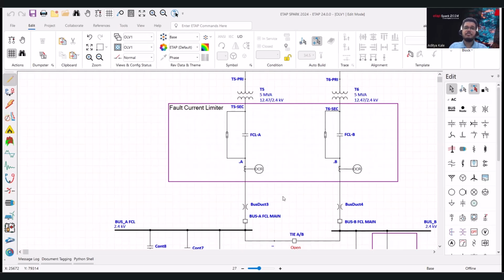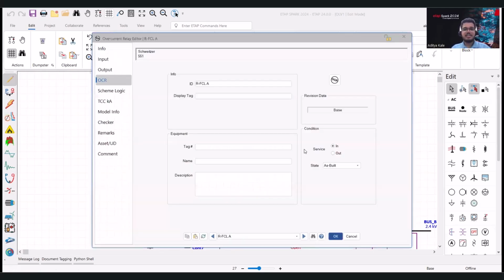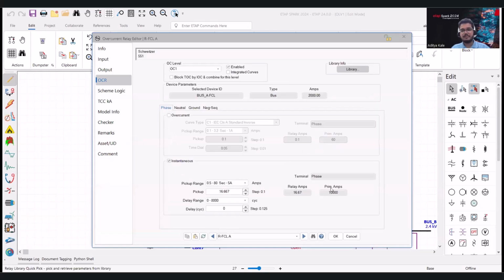They are available in various voltages and multiple trigger currents. For our case, the trigger current that we rely on is 10,000 amps. So that is how we set the overcurrent relay. The overcurrent relay needs to be, we can use any generic overcurrent relay here. I've used a Schweitzer in its place.